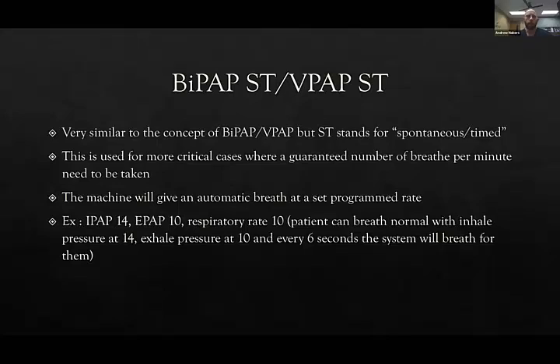And then when you add a spontaneously timed rate, the system will guarantee to give you a breath based on that rate. Now, I gave an example of a rate of 10. Now, there's 60 seconds in a minute. You divide it by 10. Every 6 seconds, the system will give a breath at that pressure of 14, regardless of what the patient's doing. It just gives you the breath.